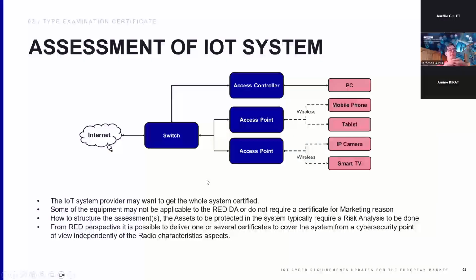And this is something that we have done before: you can evaluate the whole system as part of one or several evaluations. As you know, the standard is focusing on assets, and you can identify the assets for your whole system, and you can also consider external entities between them. Of course this needs to be discussed, and the best way to confirm this is to have the data flow diagram and risk analysis, but you can perform one or several evaluations for one system, and not necessarily one evaluation per product. This is something really to have in mind, that can facilitate your life, and also the way to compliance.